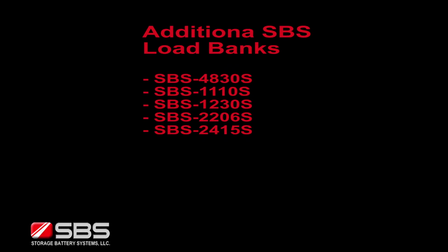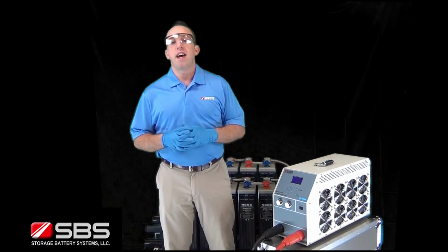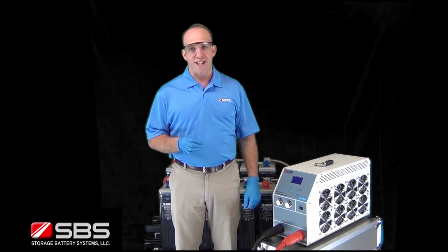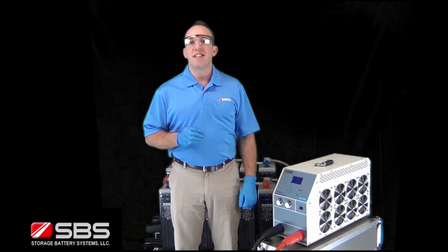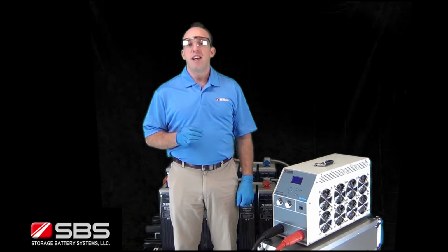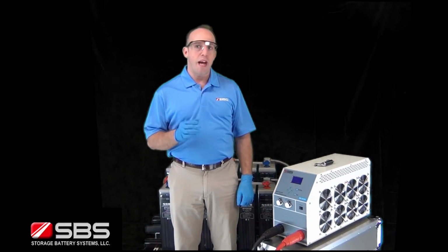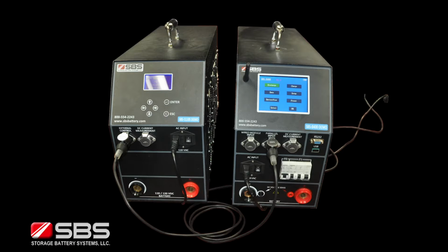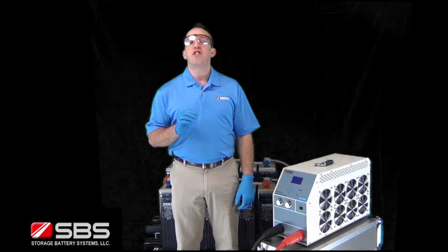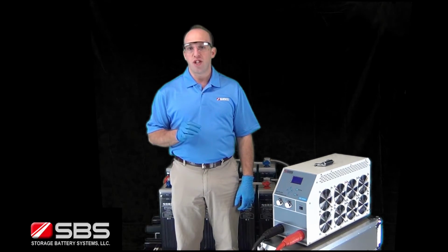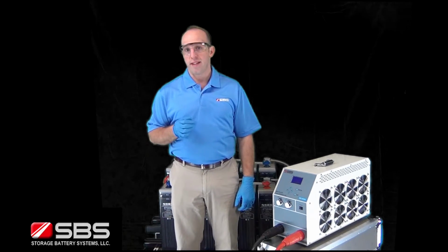It is important to use the correctly rated load bank unit while performing discharge tests. Here are all of the different SBS series load bank models. The SBS S-Series load banks are very accurate, portable, reliable, and timely with discharge results. The SBS S-Series load banks can be operated in parallel with the SBS 8400 or another S-Series load bank of the same voltage range using the external control connection cable. Each load bank must be operated within the voltage and the current limitations for that specific unit.